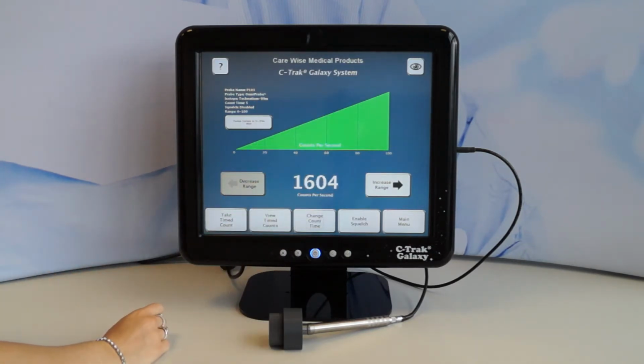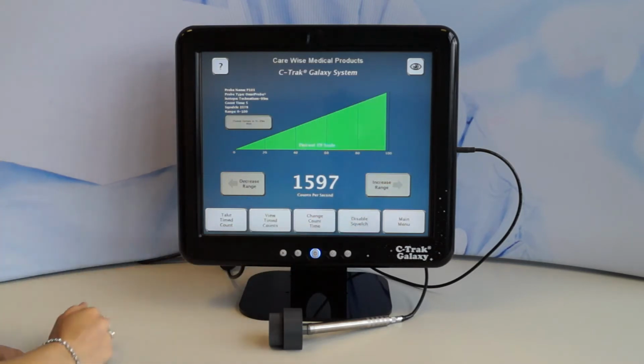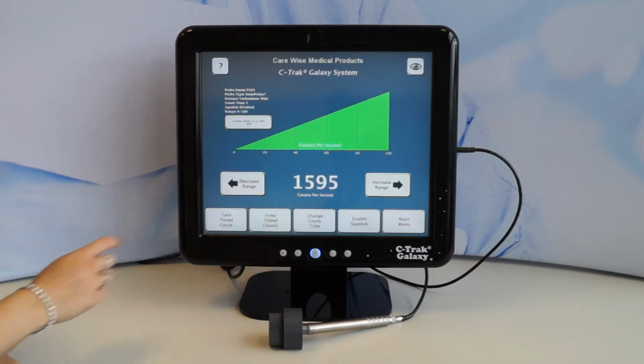The Enable Squelch button allows the user to find a hotspot and simultaneously auto-range to optimise detection of that hotspot and other sites of similar activity, whilst also removing background radiation. When Squelch is enabled, the range buttons will be disabled. To turn Squelch feature off, press the Disable Squelch button.